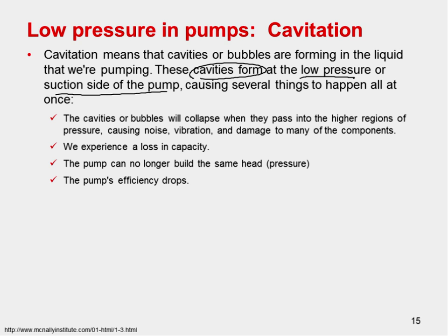Remember, suction means that you have very low pressure, lower than the atmospheric pressure. So you will have cavities of bubbles that form and pass, and then they collapse when they go into higher pressure, and that causes noise, vibration, and damage to any of the components. It's really bad. It's almost like sandblasting your pump.